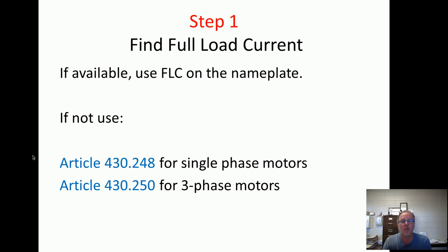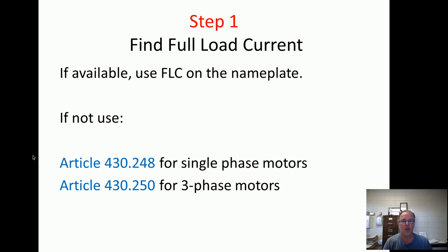Step one — what are we trying to do here? We need the amperage, the ampacity, the amperage the motor is going to be pulling. We need that full load current. Step one is very important because you've got to get the right amount of amperage from the nameplate or these articles. Step one is used in all steps, so if you get the wrong amperage, you're going to get the wrong answer.